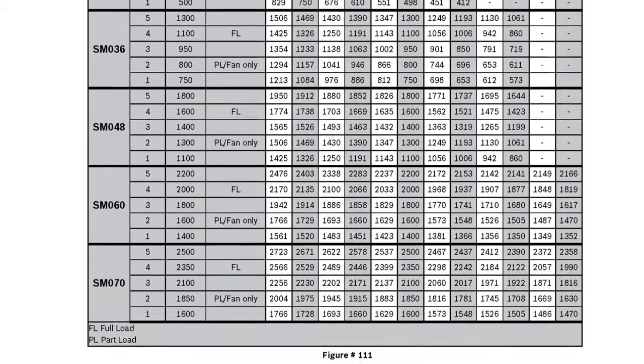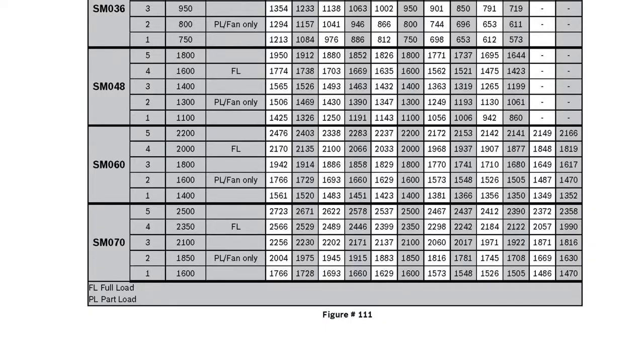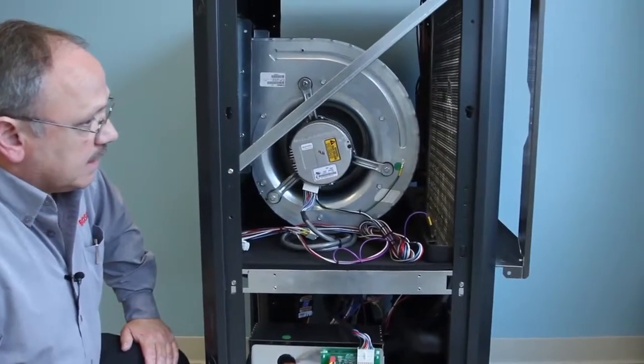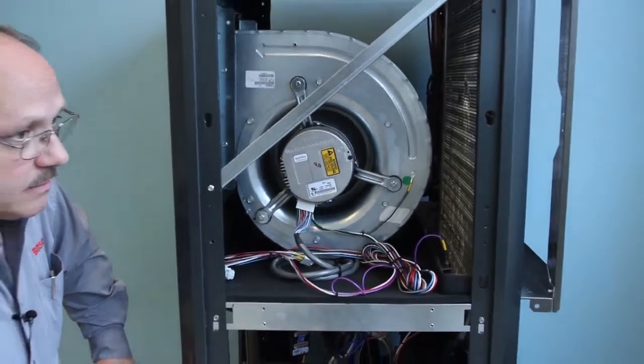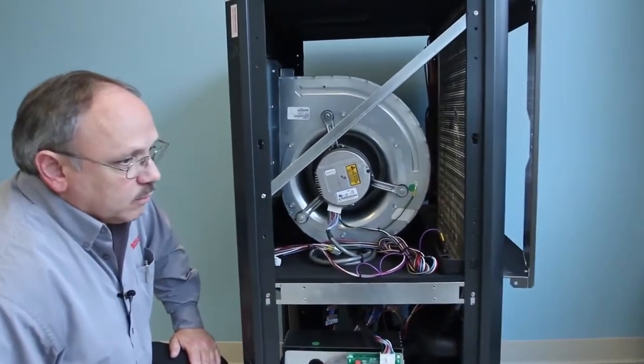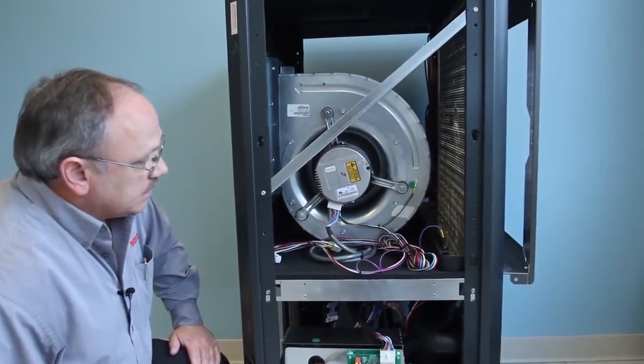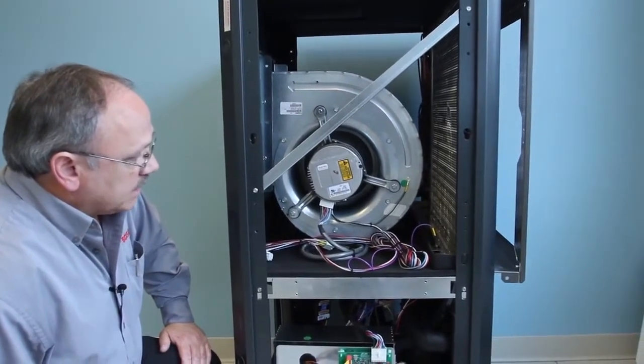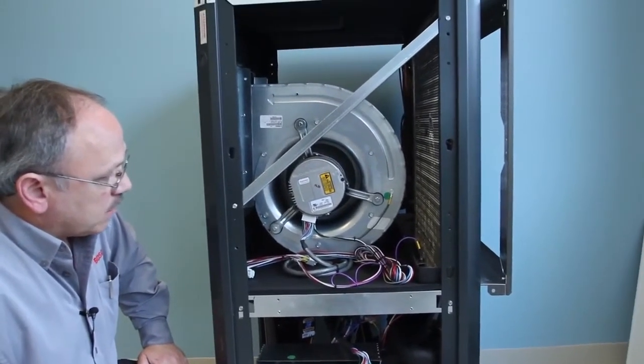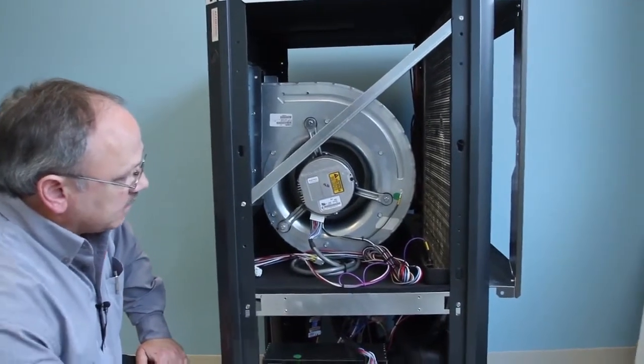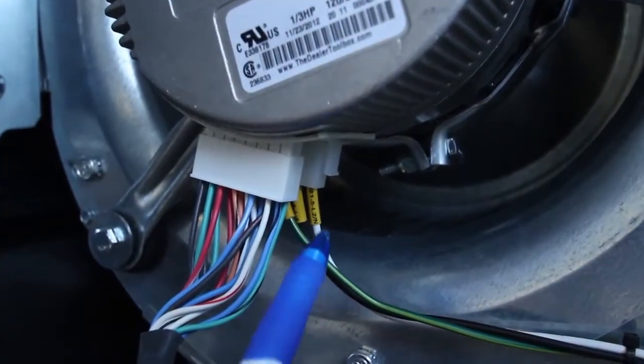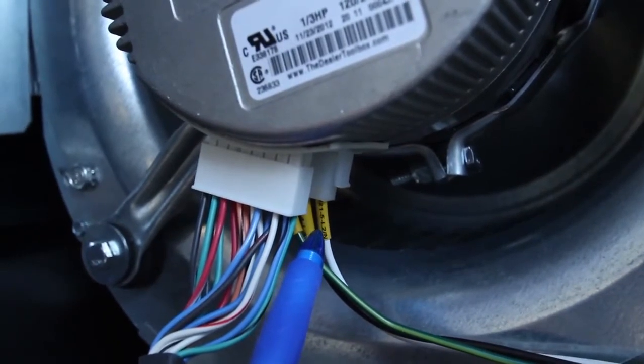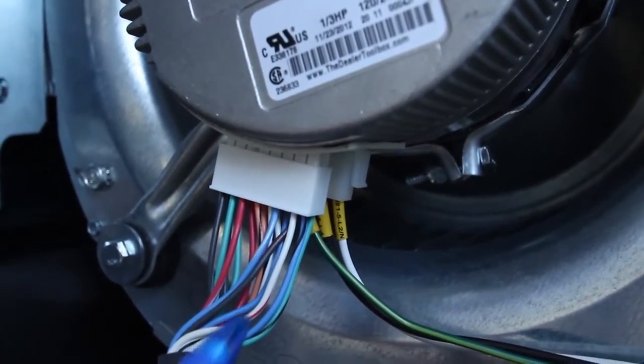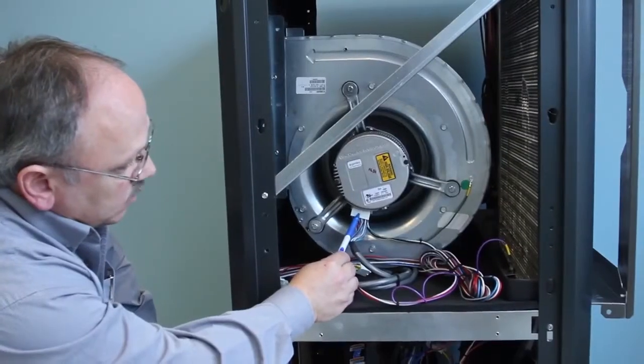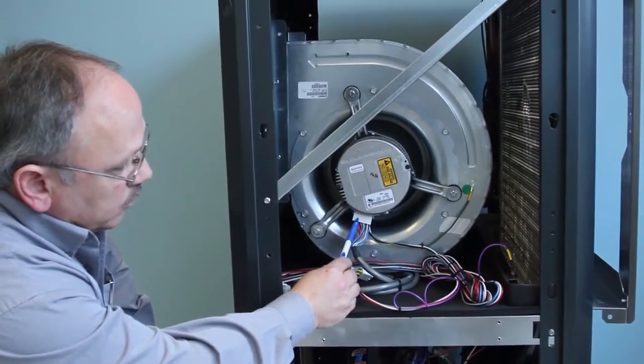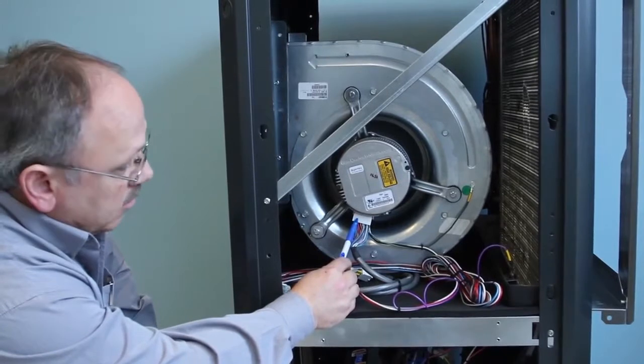One of the factory installed options that is available is the variable speed motor. The variable speed motor allows us to have the option of cool to dehumidify or passive dehumidification. The variable speed motor has 2 connectors on the back of the motor module. There is a 5-pin connector with 3 wires running to it that provide line voltage to the motor anytime power is applied to the unit. The other connector is a 16-pin wiring connector which provides low voltage inputs to turn the motor on and off.